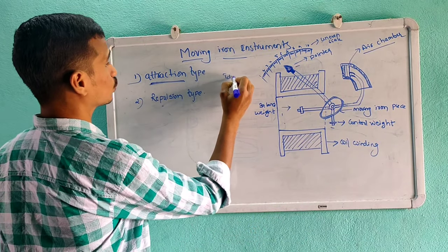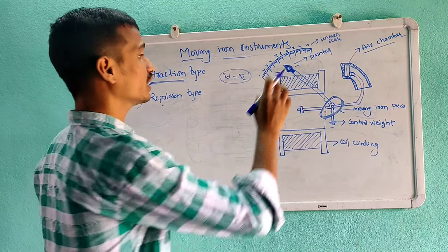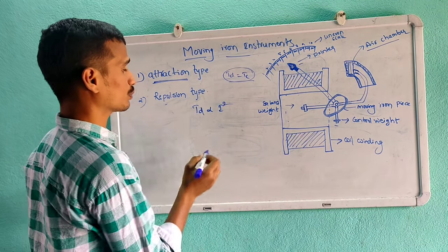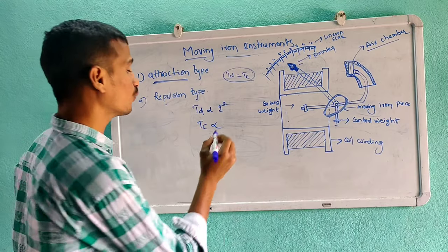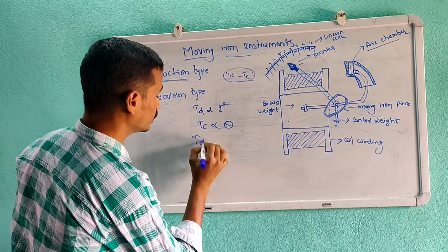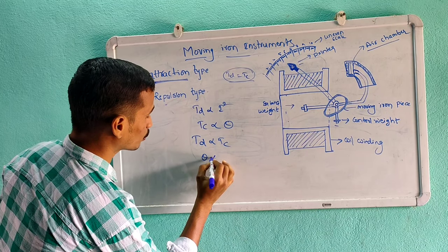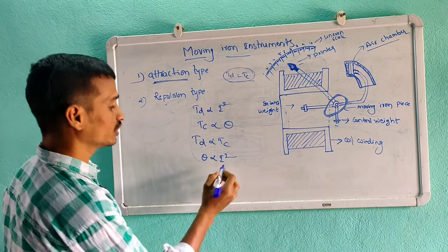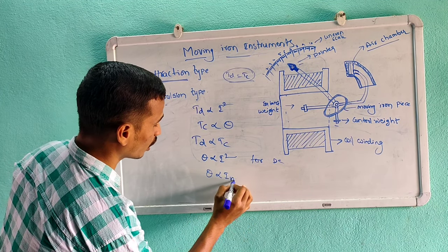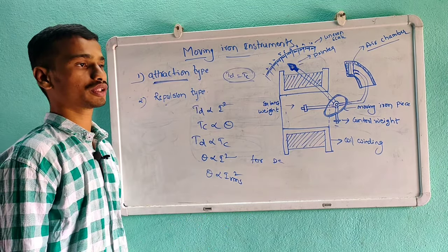The controlling torque equals the deflecting torque at steady state. The deflecting torque is proportional to I-squared. The controlling torque is proportional to the angle of deflection, so theta is proportional to I-squared. For AC, the deflecting torque is proportional to I-RMS squared. This is about attraction type moving iron instruments.